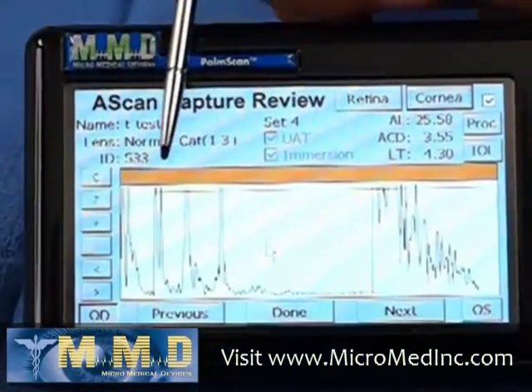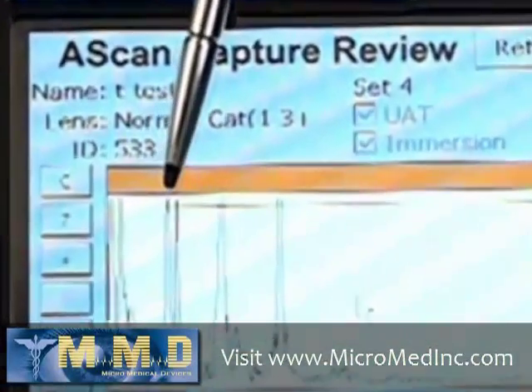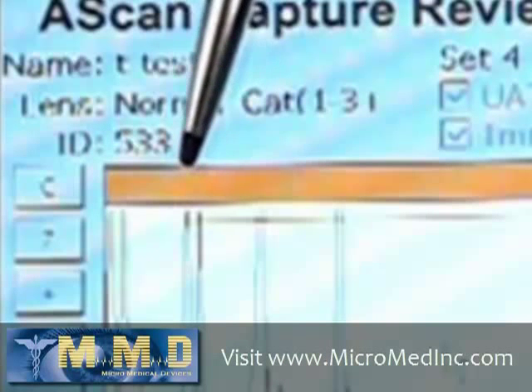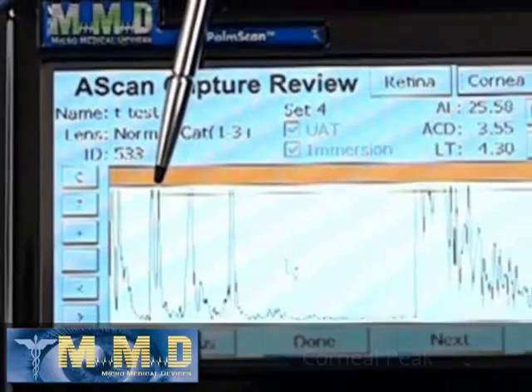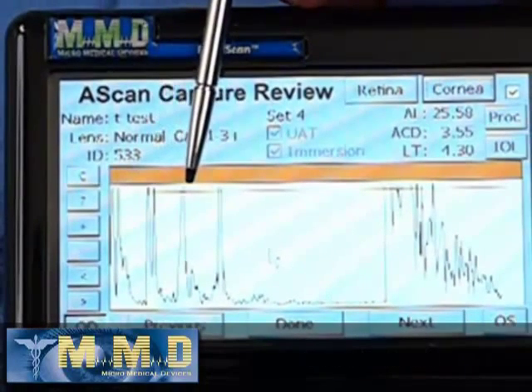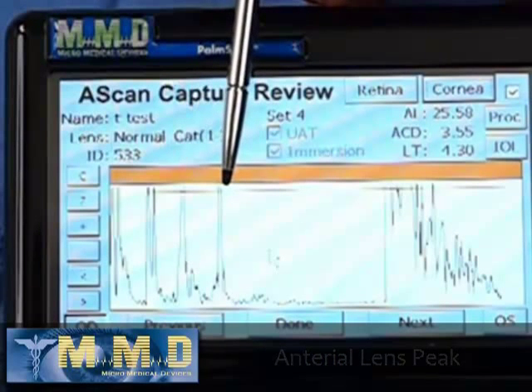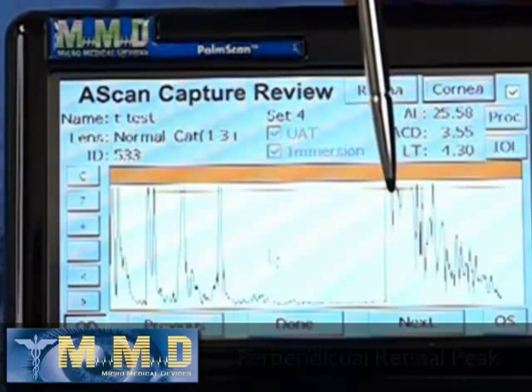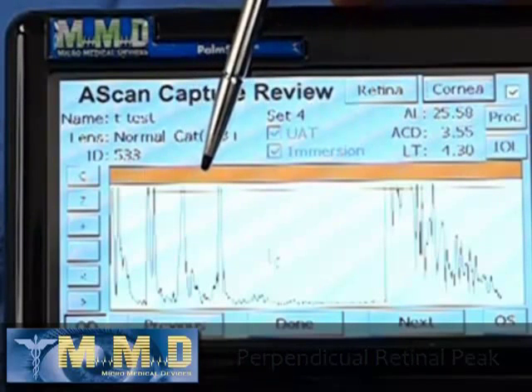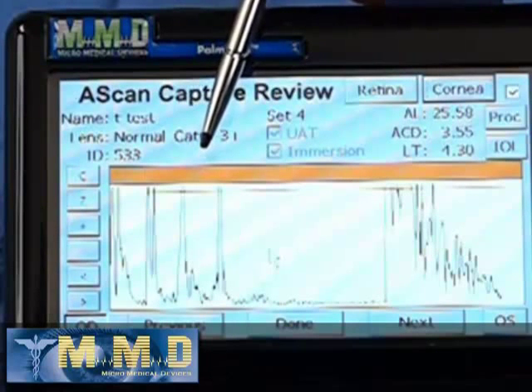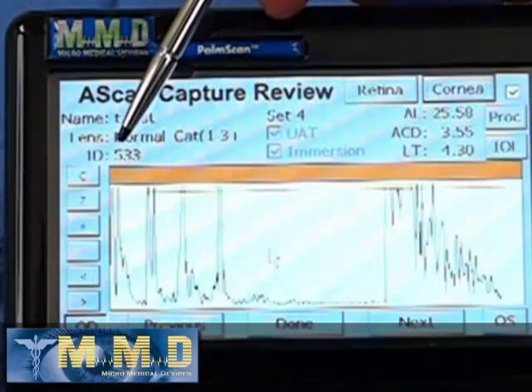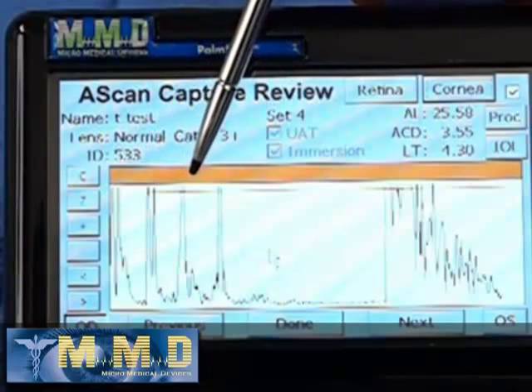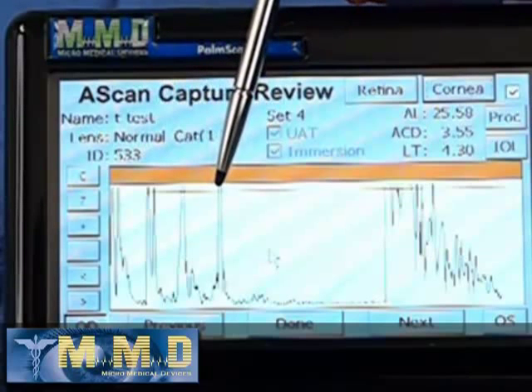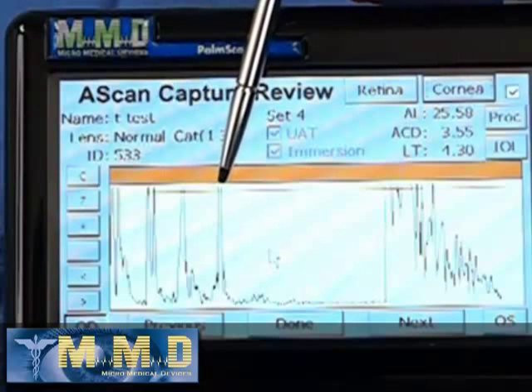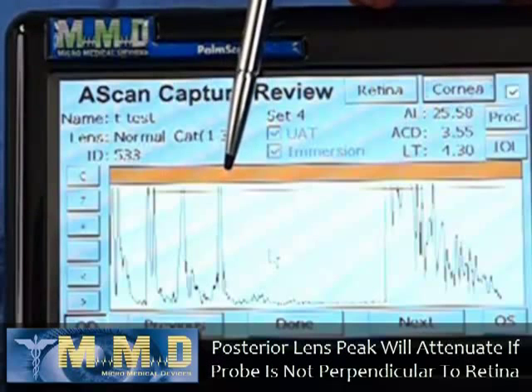The machine will reach threshold for capture when the specific structures of the eye are above the threshold line. Specifically, the machine is looking for the corneal peaks, the anterior lens peak, the posterior lens peak, and the perpendicular retinal peak. Now, if the patient is not directly looking at the probe, so if the patient's retina is not perpendicularly aligned with the probe, the number one peak that will be reduced or attenuated would be the posterior lens spike.